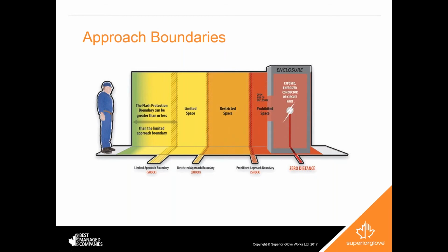And then we have our limited approach boundary. This is the minimum distance where unqualified personnel may safely stand. So someone like myself, who has no formal training in arc flash, that's the closest I could be to our energized equipment. No untrained person can approach any closer than this boundary, and the qualified people who are allowed to go past there have to have the appropriate PPE. They have to be trained to perform the required work, and they have to have a reason to actually go across this boundary.